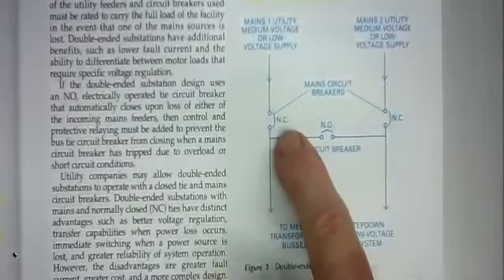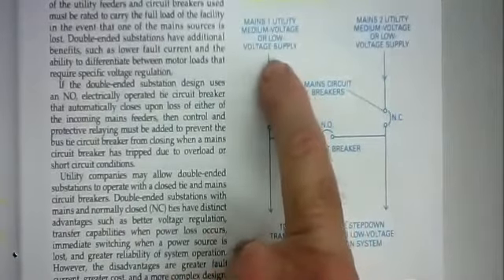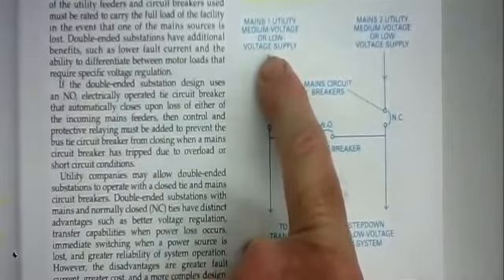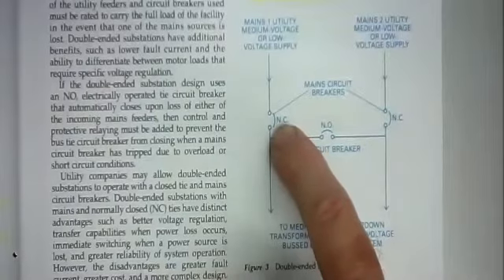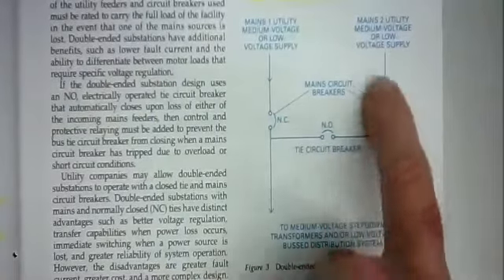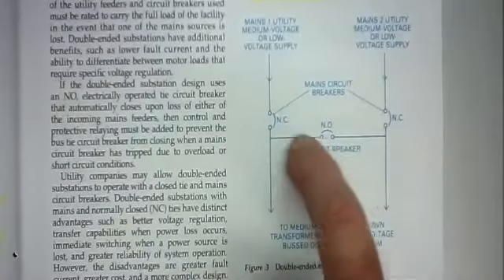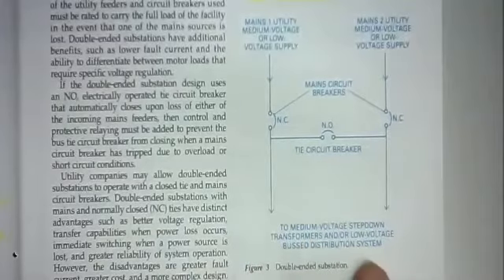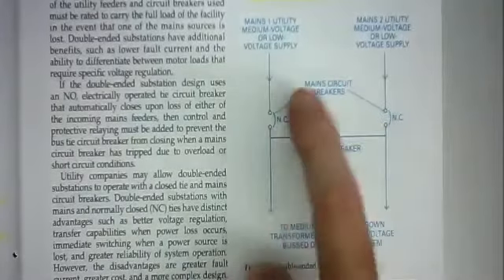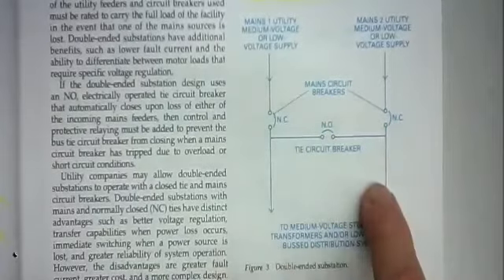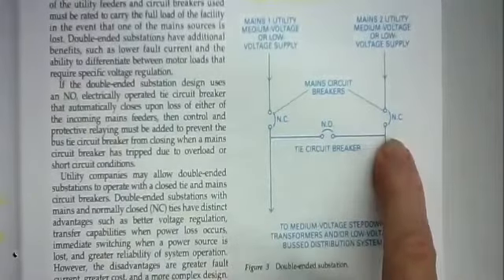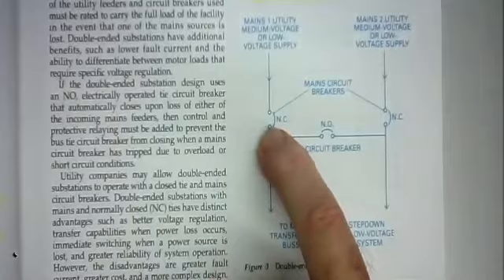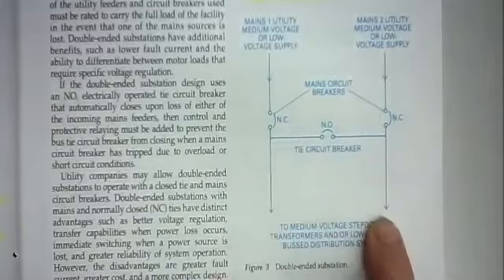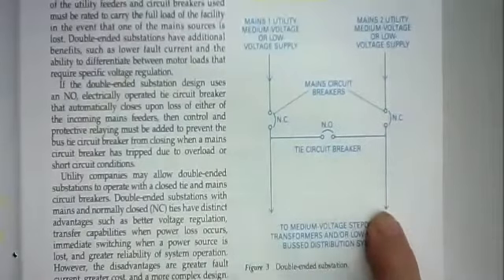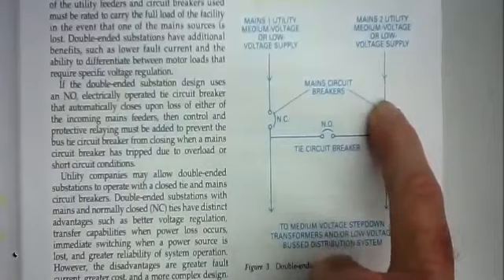If you close the tiebreaker, if something happened at this substation, a bus went off the road and crashed into the substation and took it out, they could open this normally closed circuit breaker and they could close the tiebreaker, and this second utility is large enough to carry the entire load of the hospital. That's why we used to call them redundant, because they had enough service on each of these to run the entire facility. So either one of these can be taken out and they can open the circuit breaker from that utility and close the tiebreaker, and now they can feed the entire facility with just the one side. And this is a one-line diagram. This is actually three-phase coming in, three-phase 480 or three-phase 13.8, whatever it is they have coming in.